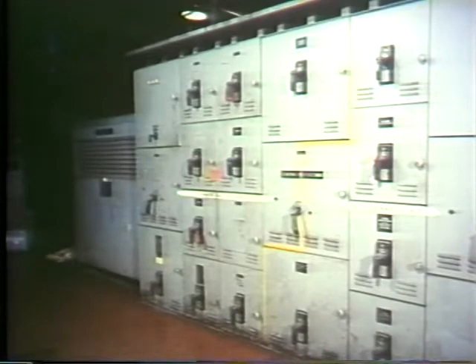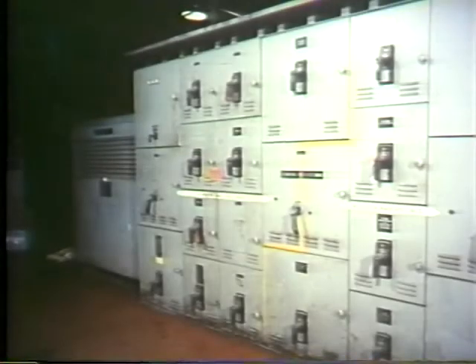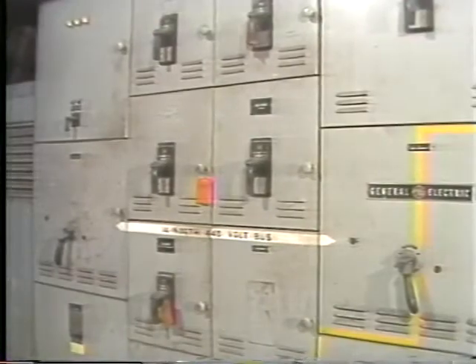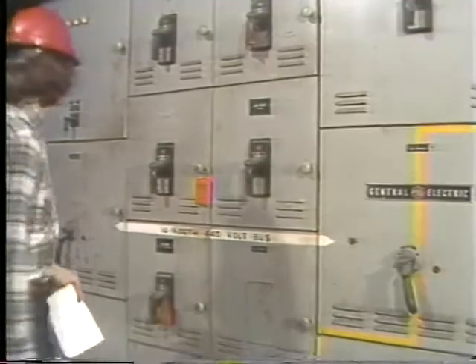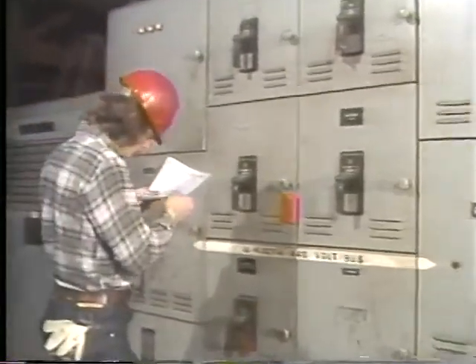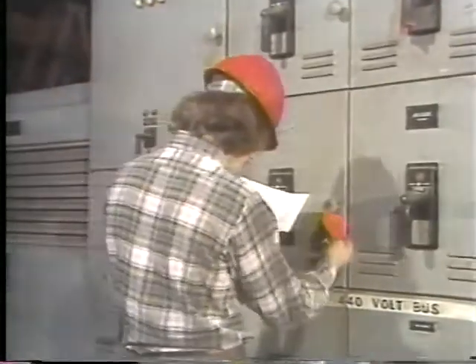A temporary feed's been hooked up to spare breaker 303 at this load center. The job is to remove the feed from the de-energized breaker load terminals. But since the rest of the load center handles essential equipment, the main bus will be hot. Before starting, the electrician checks the print and the tag to make sure he's on the right breaker.